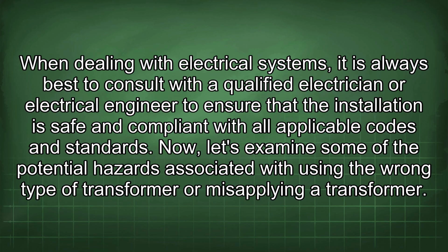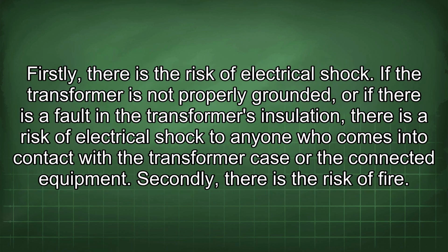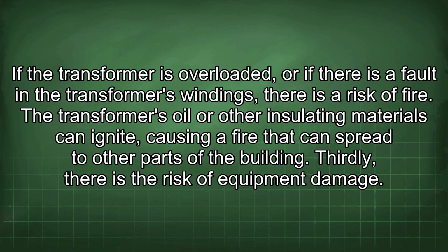Now, let's examine some of the potential hazards associated with using the wrong type of transformer or misapplying a transformer. Firstly, there is the risk of electrical shock. If the transformer is not properly grounded, or if there is a fault in the transformer's insulation, there is a risk of electrical shock to anyone who comes into contact with the transformer case or the connected equipment. Secondly, there is the risk of fire. If the transformer is overloaded, or if there is a fault in the transformer's windings, there is a risk of fire. The transformer's oil or other insulating materials can ignite, causing a fire that can spread to other parts of the building.